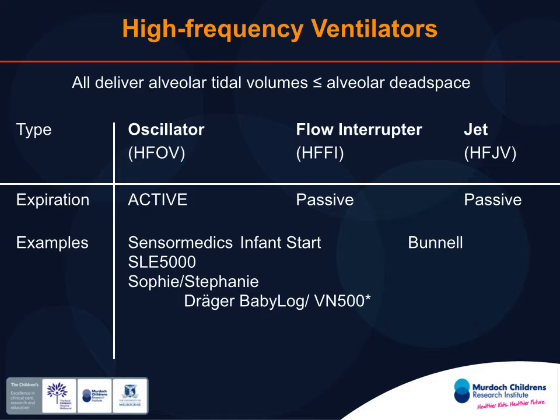We then had a group of ventilators which are really more flow interrupters. So it's fast flow of gas, and they quickly interrupted that flow, and they had a more passive approach to expiration. The Draeger devices sort of would fit somewhere in between because of the use of Venturi effect for expiration. I'll show you at the end that this probably, at least for these devices, isn't relevant anymore. And essentially, the true flow interrupters aren't on the market.